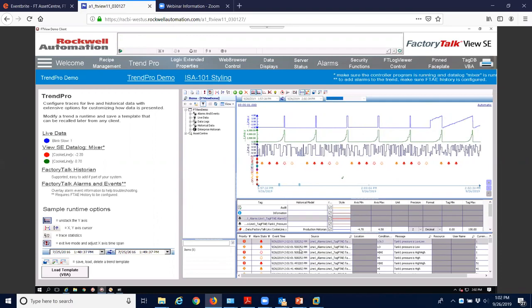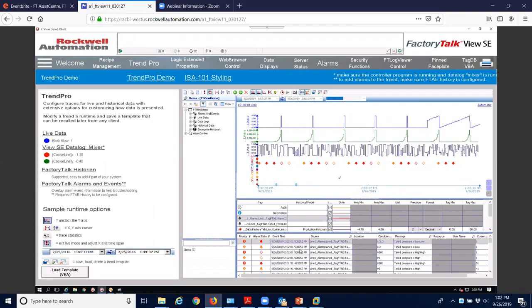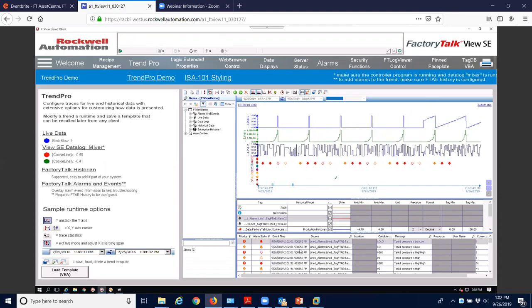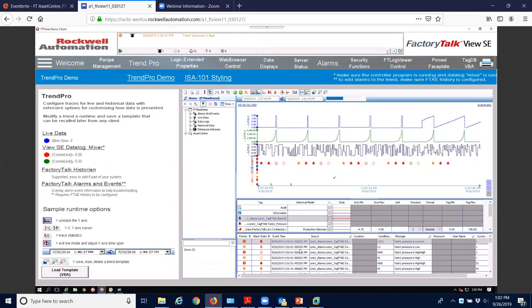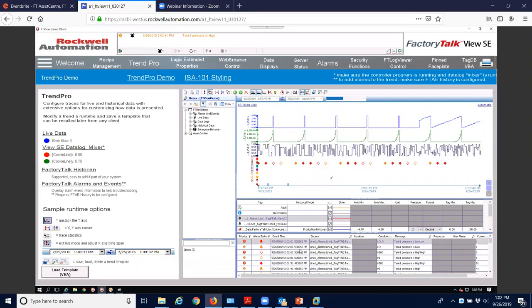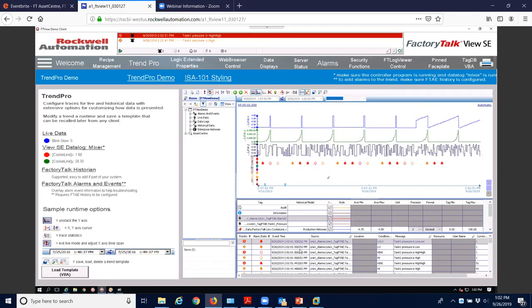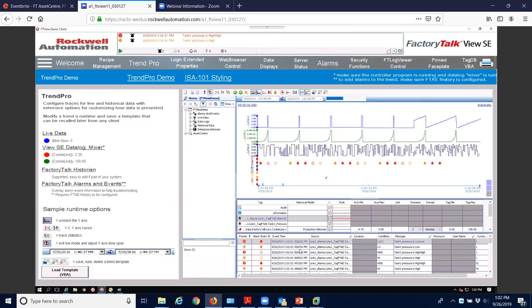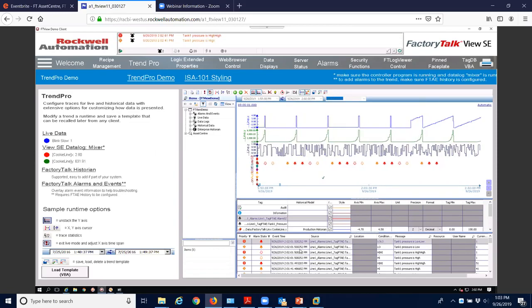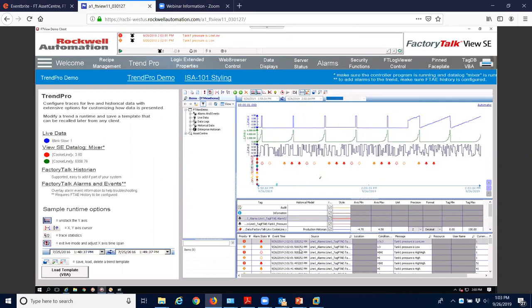I think I mentioned this in passing, but I didn't really focus on it. One of the options that you also have in FactoryTalk View 11 is you can now do production events. So there's an alarm and event server, if you guys have ever seen that. Typically that was for your alarms. So now what you can also do is if anybody's ever asked to be able to do kind of an audit log of who's going in, what button pushes are happening, and you didn't have AssetCentre, you pretty much needed to try to dump everything into a historian or a data log.